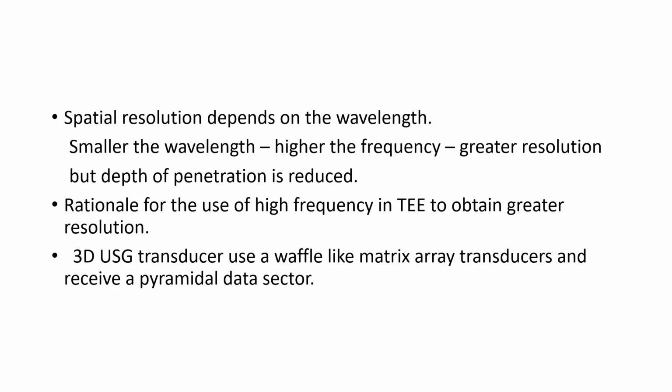Smaller the wavelength, higher is the frequency, and greater is the resolution. But the depth of penetration of the ultrasound waves is reduced. And this is the reason why we use a high frequency probe in transesophageal echocardiography. To get a higher resolution, we need a higher frequency or smaller wavelength ultrasound waves. But using the higher frequency and smaller wavelengths causes the depth of penetration to be reduced. Hence, the transducer is introduced into the esophagus using an endoscope to obtain a greater resolution.